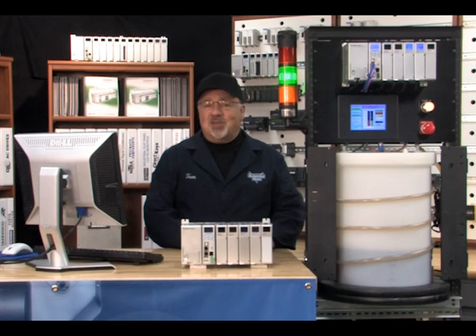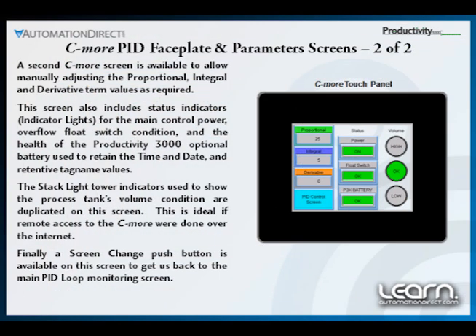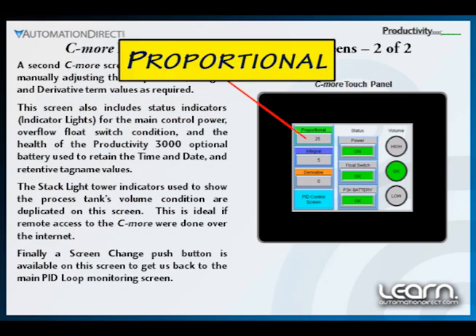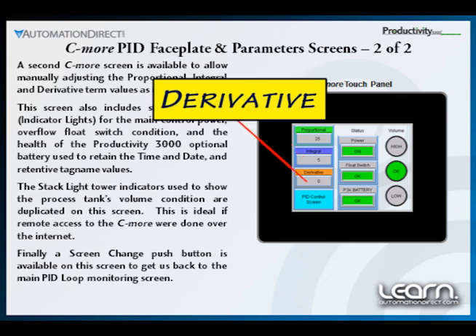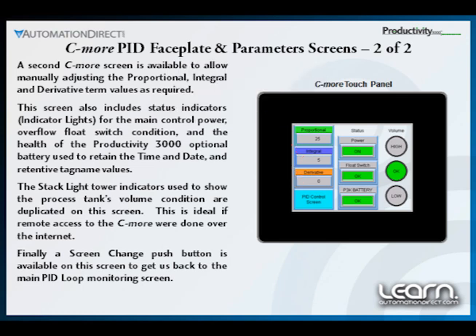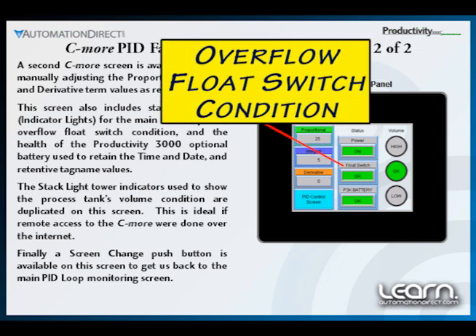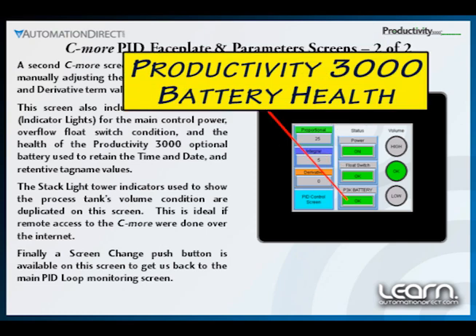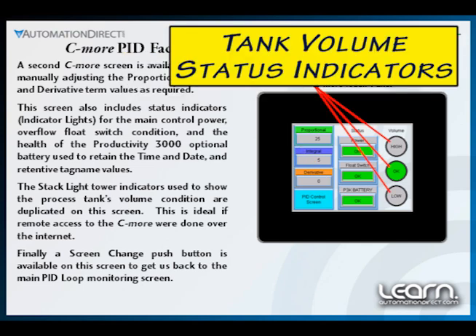I've added a second C-more screen to allow manually adjusting the proportional, integral, and derivative term values as required. The screen also includes status indicators for the main control power, overflow float switch condition, and the health of the Productivity 3000 optional battery used to retain time and date, and retentive tag name values. The Stack Light tower indicators that show the process tank's volume condition are also on this screen.